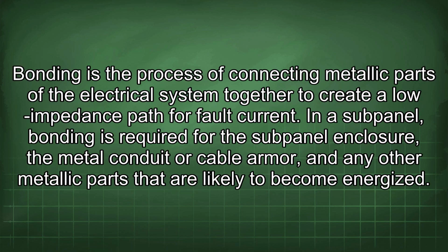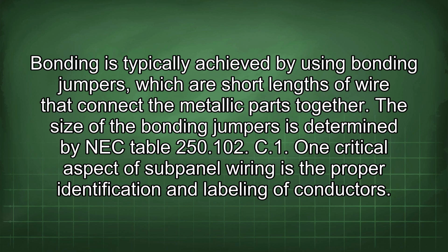Bonding is the process of connecting metallic parts of the electrical system together to create a low impedance path for fault current. In a subpanel, bonding is required for the subpanel enclosure, the metal conduit or cable armor, and any other metallic parts that are likely to become energized. Bonding is typically achieved by using bonding jumpers, which are short lengths of wire that connect the metallic parts together. The size of the bonding jumpers is determined by NEC Table 250.102(C)(1).